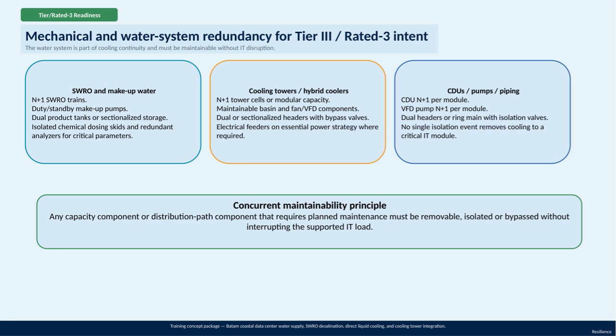Regarding CDUs, pumps, and piping, each module has CDU N+1 redundancy and VFD pumps set up with the same redundancy principle. Cooling distribution uses dual headers or a ring main with isolation valves, ensuring no single isolation event removes cooling to any critical IT module. Finally, the concept of concurrent maintainability is fundamental here. It means that any component within capacity or distribution that needs planned maintenance can be isolated or bypassed without disrupting the IT load it serves. This principle guarantees that maintenance activities never interrupt cooling continuity, safeguarding the data center's operation.